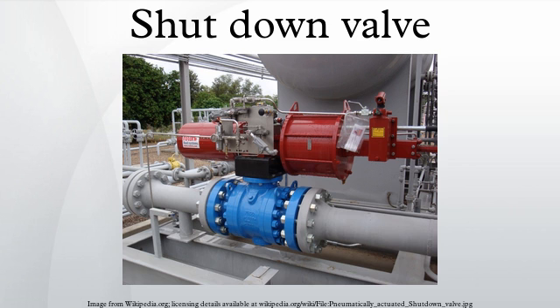As shutdown valves form part of a safety instrumented system, it is necessary to operate the valve by means of an actuator. These actuators are normally fail-safe fluid power type. Typical examples include pneumatic cylinder, hydraulic cylinder, and electro-hydraulic actuator.